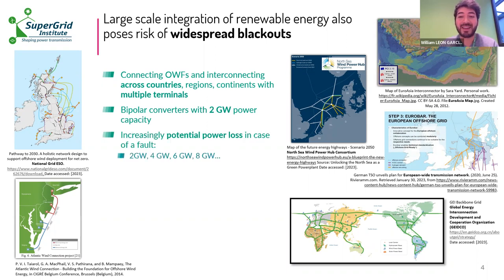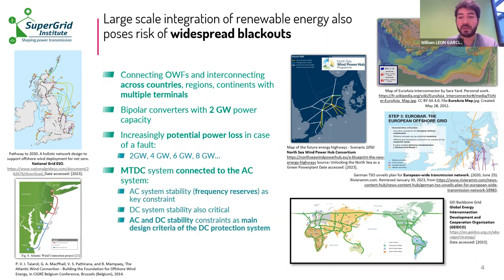We're now talking about increasing the number of terminals and power in what we call a multi-terminal HVDC system. Since the power increases, so does the risk of a fault, leading to a potential sudden loss of two, four, six gigawatts or more. With increasing scale and complexity, we must consider the risk of widespread blackouts. The MTDC system is connected to the AC system as well, so the stability of both systems is crucial. Currently grid codes specify rules to maintain AC network stability, but these rules are limited to each country, so we need better knowledge on DC side security constraints.